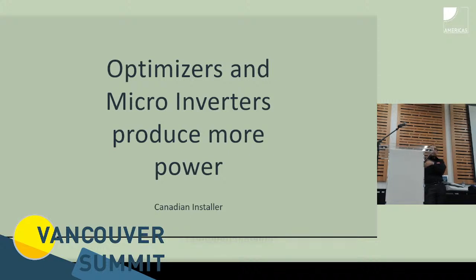Never—no, it would be in winter, or if you've got chandelier-style roofs. It would usually be either in fall or in deep winter. Because outside of that, if you make a fair comparison between a string inverter and a microinverter, your gross oversizing on the string inverter actually costs you less than throwing in more electronics. And the more electronics you throw in, the higher the failure rate, since electronics will fail. So in the long run, talking about the cost of O&M, or looking after the system over 20 years, you'll see you're either breaking even, or you've got less upkeep and maintenance on a single inverter located in an easier to access place.